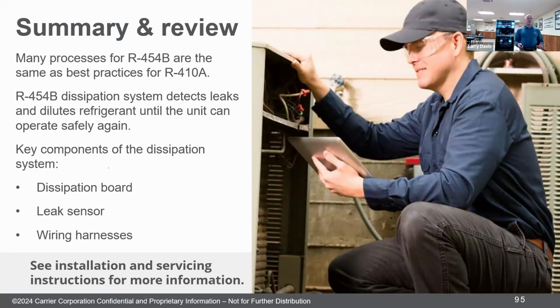The 454B dissipation system, that's the process that we're using to mitigate any risk of flammability if there happens to be a refrigerant leak. Components of that system are the dissipation board, leak sensor, and the wire harness that interwires with your system to shut down the heating and the air conditioning call, and run the fan to spread that refrigerant out through the air and dissipate it to mitigate our risk of it becoming flammable.